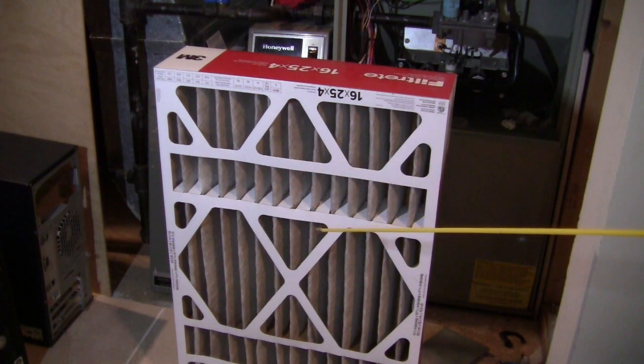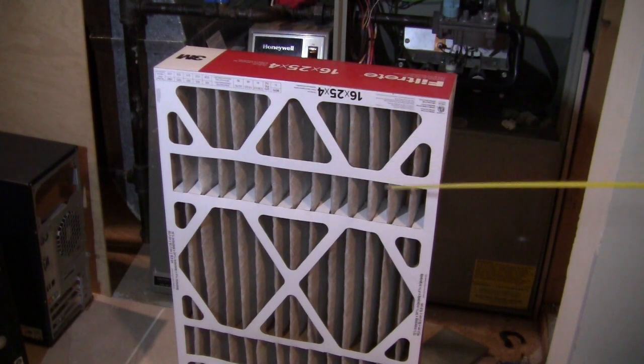But the problem is, if you put two layers or a very thick filter, the air flow through the filter is going to be slow. So your heater or your air conditioner, the efficiency will drop, maybe drop a lot. So in that kind of situation, for a normal family, we just suggest picking the medium layer, which will be okay. Don't put in the very aggressive stuff.